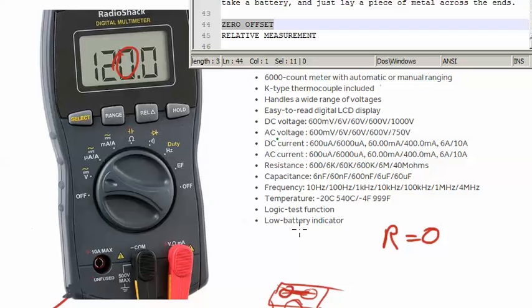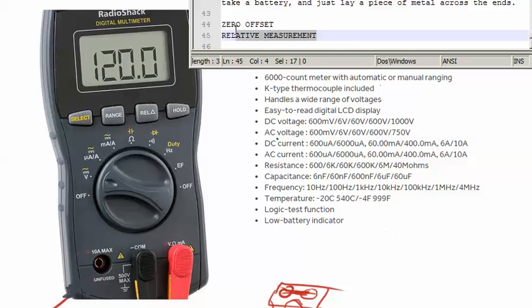You need to hit the rel delta, and then it says the meter is in manual mode, and take the measurements with the rel delta displayed. But if you want relative measurement, it is also available for voltage, microamps, milliamps, ohms, farads, and hertz functions. You can take a measurement relative to a reference value.